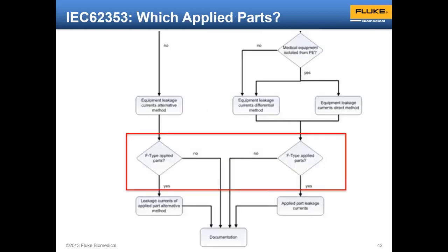All right, so we're back to the lead isolation tests, the F-type applied parts tests, and the question in that decision tree from the 62353. If there are no F-type applied parts, the answer is no here, then we just document the leakage current tests that were done before this. If there are, then we have to do the applied part tests, for whichever method that we're using.